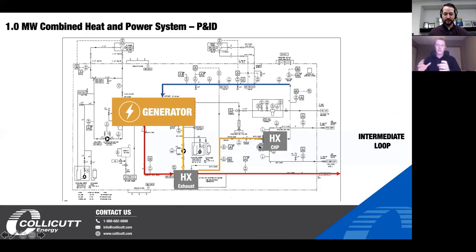The CHP heat exchanger is where we transfer the heat from the CHP to the building. On the other side of the heat exchanger, cold water comes from the building, passes through this plate-and-frame heat exchanger — a water-to-water heat exchanger — and then goes back. You always have a hot side and a cold side; we're transmitting heat from hot to cold. These heat exchangers can be very efficient. That cold water then goes back into the generator.